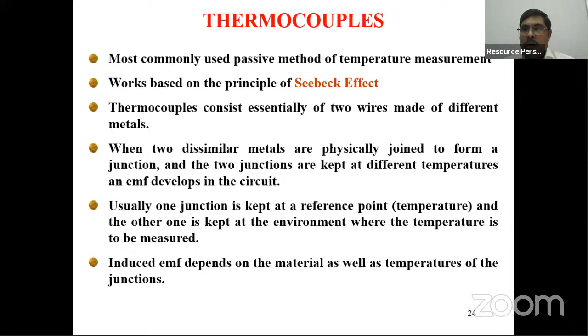So here is the circuit. And as I told, there are two dissimilar metals, copper and then Constantan. Copper is a positive one, Constantan is a negative one. So with the help of these two metallic wires, you form two junctions. One junction is maintained at the reference point, which is normally at 0 degrees, and another is at the unknown temperature. So when you connect this thermocouple, EMF will be generated. This EMF is directly proportional to the temperature difference between these two junctions. And also it depends on the material property, that means what type of thermocouple it is.